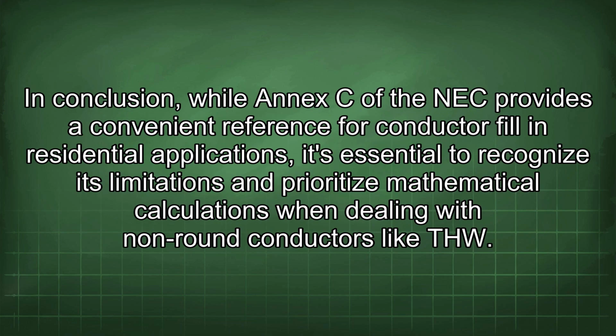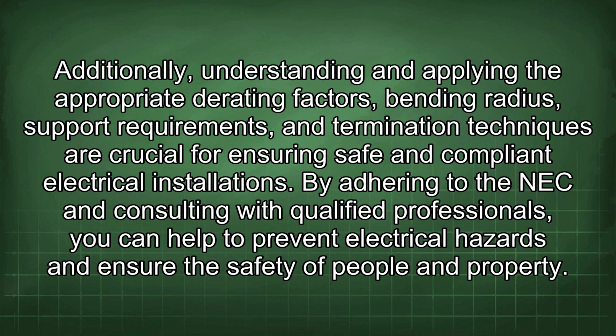In conclusion, while Annex C of the NEC provides a convenient reference for conductor fill in residential applications, it's essential to recognize its limitations and prioritize mathematical calculations when dealing with non-round conductors like THW. Additionally, understanding and applying the appropriate derating factors, bending radius, support requirements, and termination techniques are crucial for ensuring safe and compliant electrical installations. By adhering to the NEC and consulting with qualified professionals, you can help to prevent electrical hazards and ensure the safety of people and property.